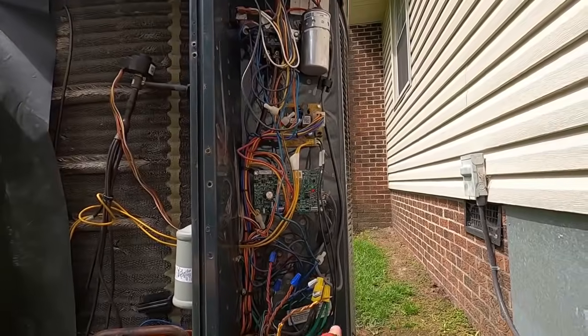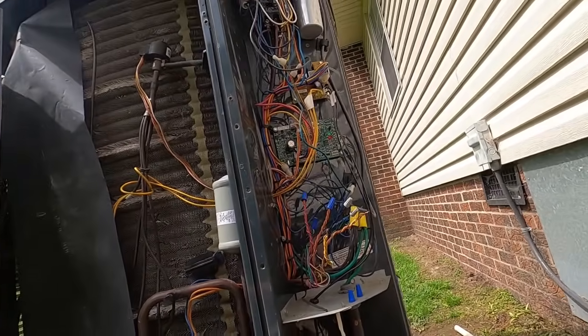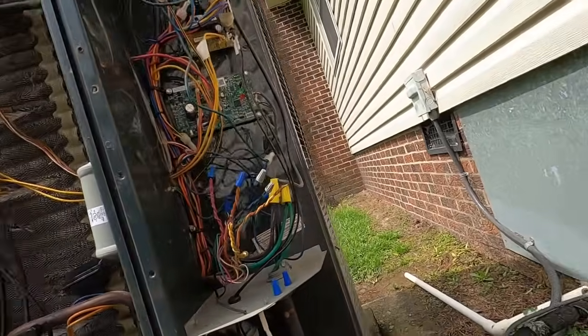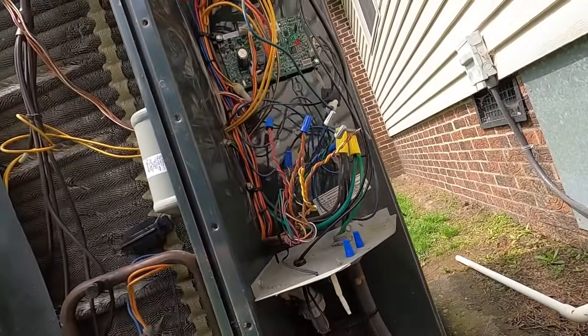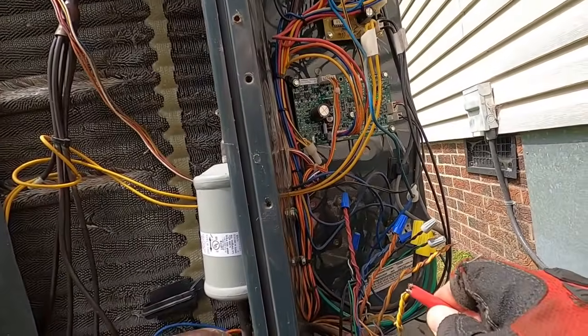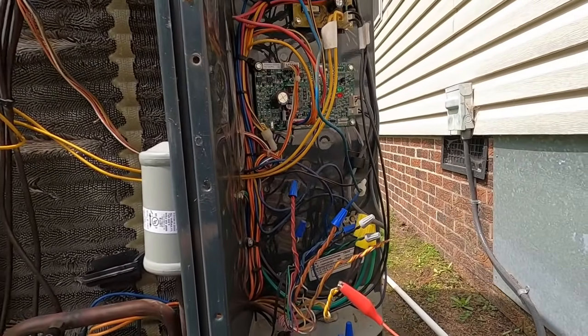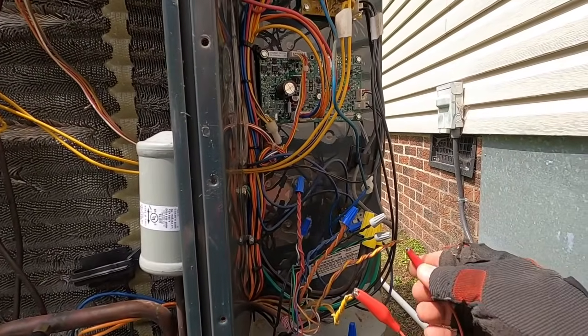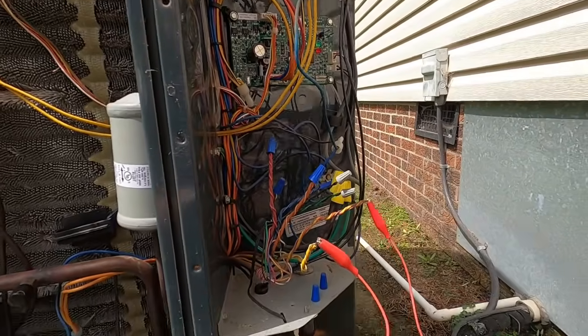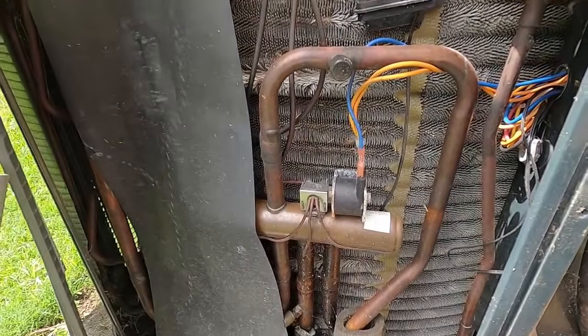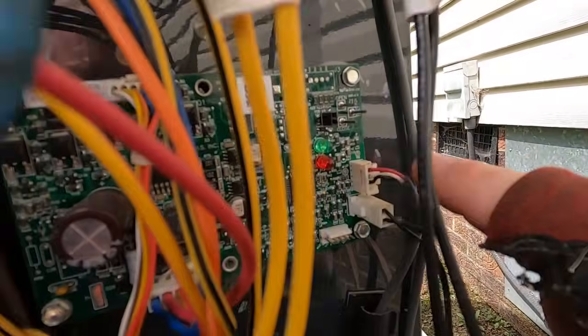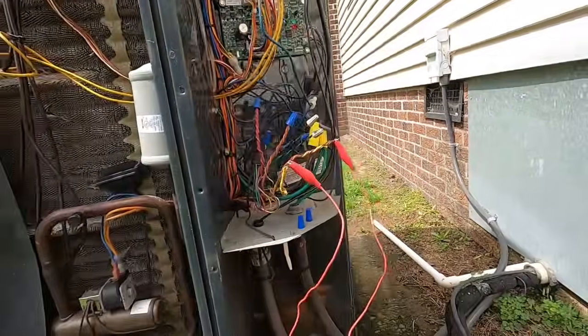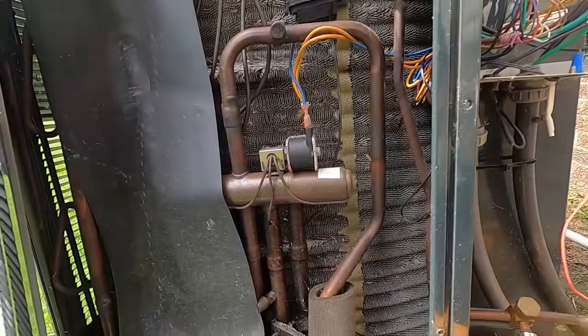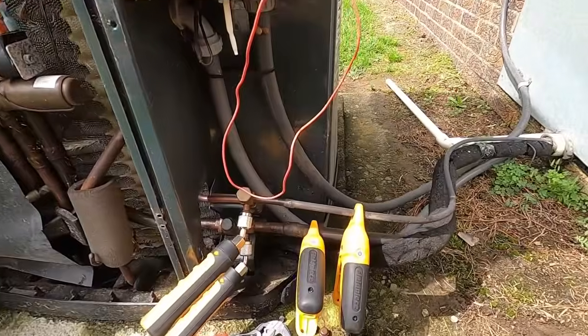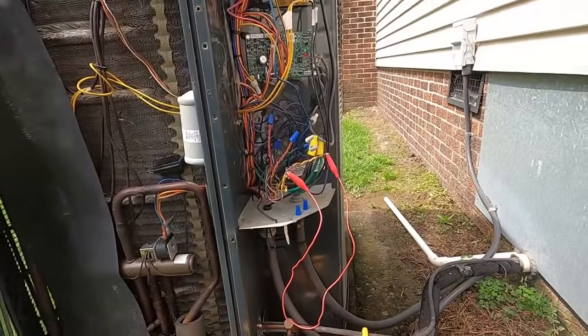for whatever reason, when it was going into second stage, which I'm going to jump it out real quick, put it back in second stage just out of curiosity, and this will energize back to the indoor unit, and it'll ramp that motor up. Heard that compressor sound. Went up into second stage. Our light's now flashing twice for second stage. We'll let it run a little bit, let these pressures stabilize out, but you may never have a problem again.